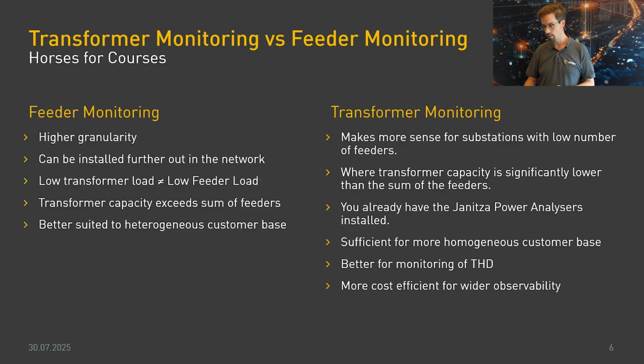That would be one use case. Finally, it's more cost effective to do it this way: a single transformer monitor is less costly than, say, 7 feeder level monitors. So if you're constrained on budget, this is a good place to start, and it may help you define where you want to do feeder level monitoring.